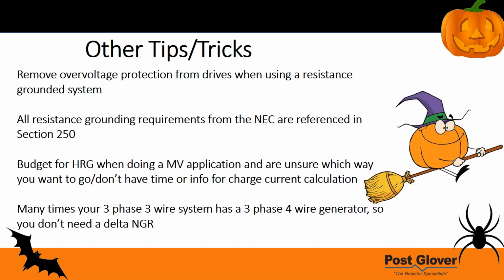You remove overvoltage protection from drives when using a resistance ground system. We've had enough drives go up in smoke to know this is definitely something you want to think about. So you have MOV protection - we're talking about a ground path on your system. It's going to be grounded, you'll have a parallel path, it's going to be solidly grounded, and you'll get more current through that than through your resistor. Your drive is going to smoke.